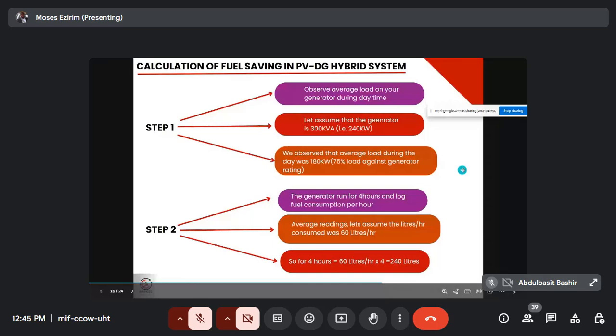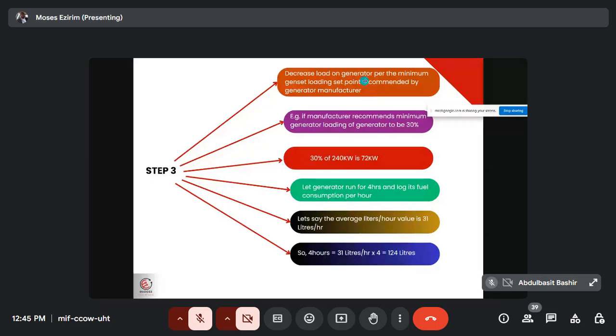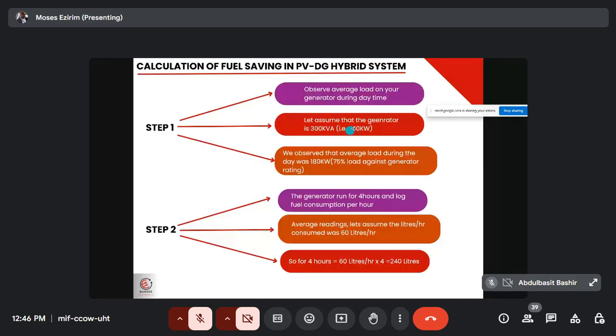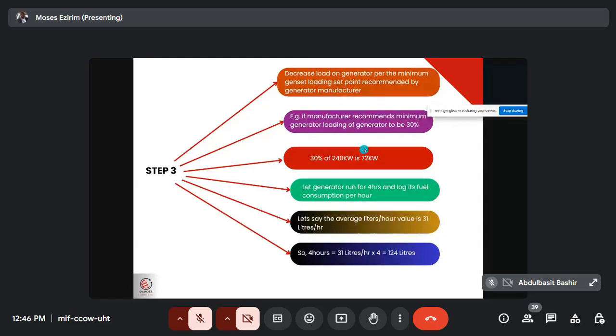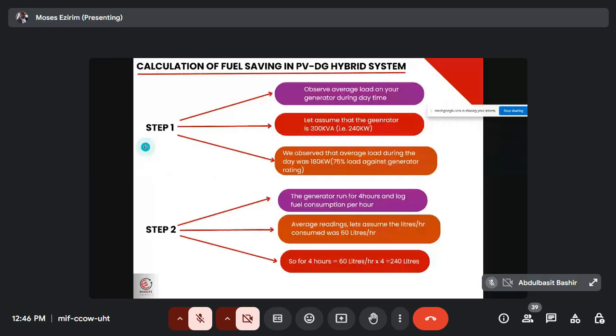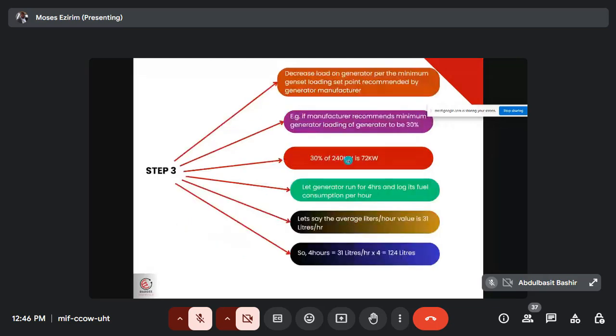Now, in this case, in step 2, I've not introduced my PV. All right. Now, decreasing the load on the generator to the minimum genset load set point recommended by the generator manufacturer. Like I mentioned to you, some generators recommend 25, 20, but let's assume that in this case it is 30% of this generator capacity. Remember, this is the capacity of the generator. 30% of this will give us 72. So this is the base load, which means I must not run below it. I'm still running the same generator for 4 hours.